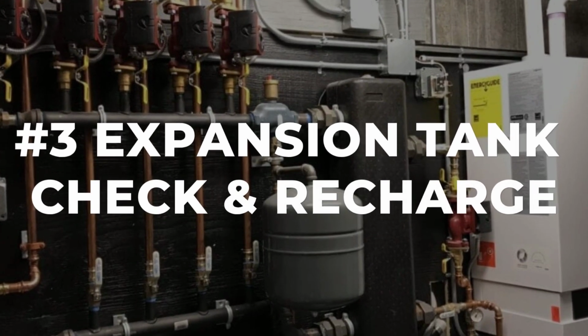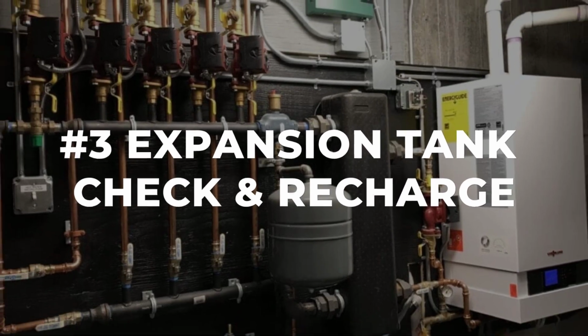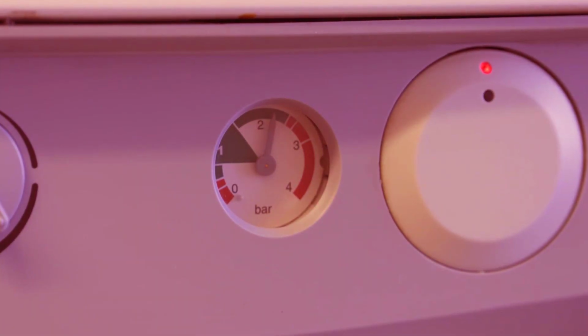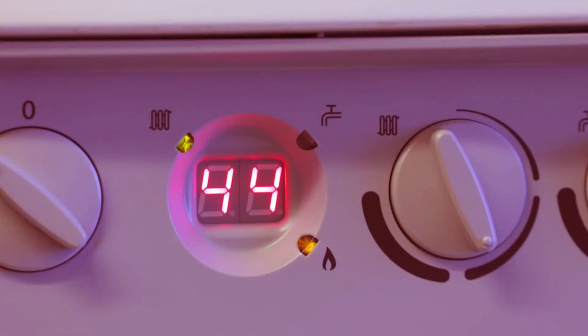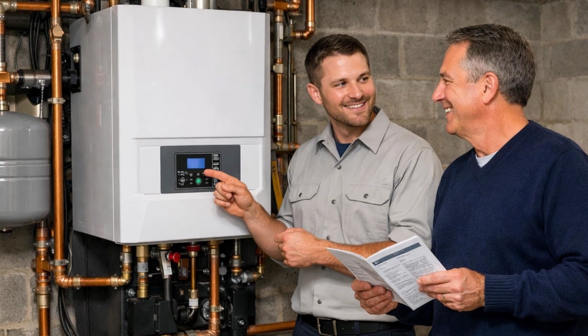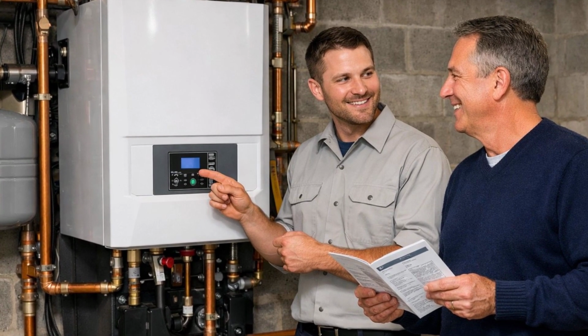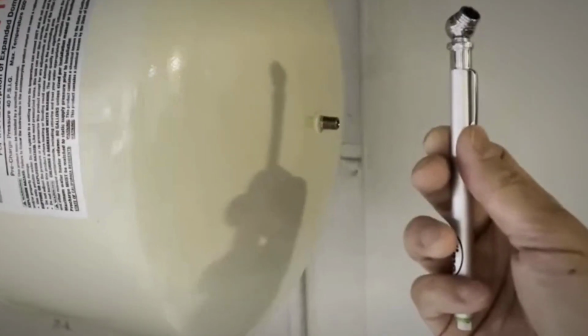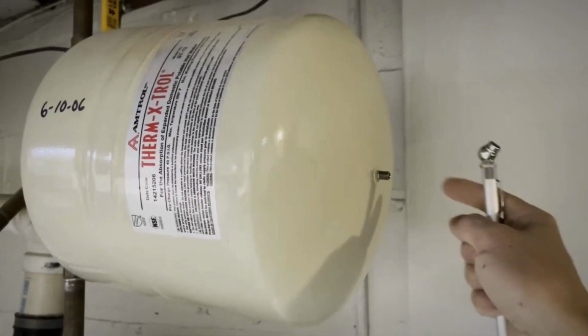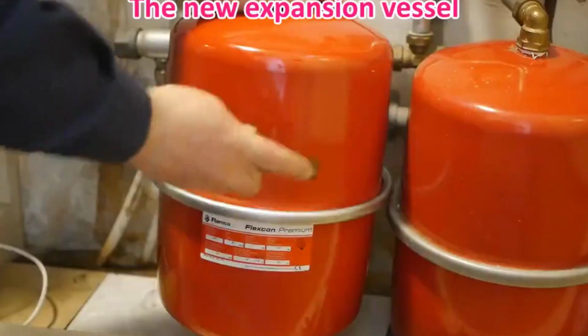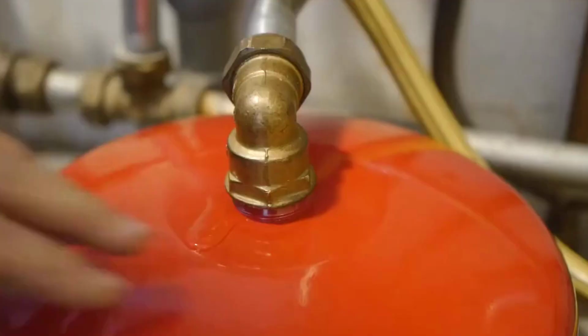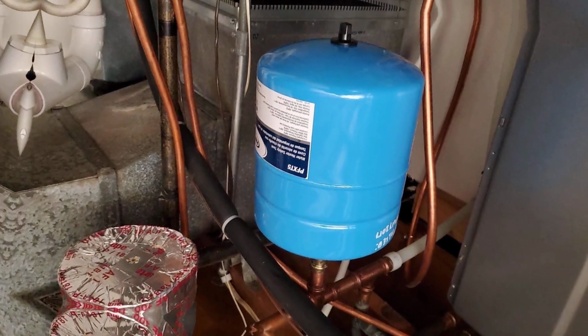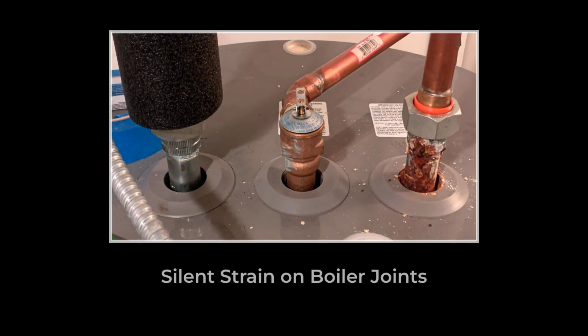Number 3 is the expansion tank, the silent pressure valve between your boiler and a cracked heat exchanger. A waterlogged expansion tank is a time bomb for overpressurization, and it is dead simple to catch before it destroys your system. Start with the tap test. With the boiler cold, tap your knuckles or a screwdriver handle against the tank. A hollow ring means air is present, just as designed. A dull, heavy thud means water is where air should be. A failed diaphragm and mounting stress on every joint and weld downstream.